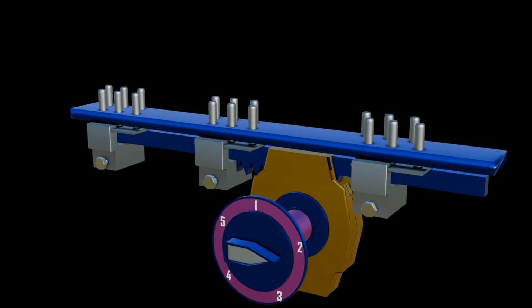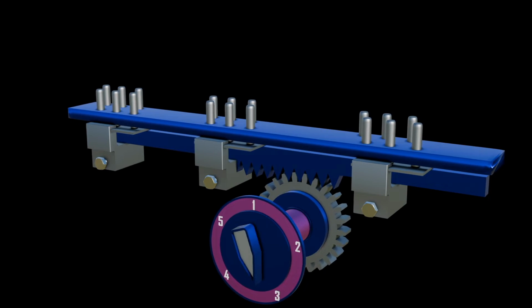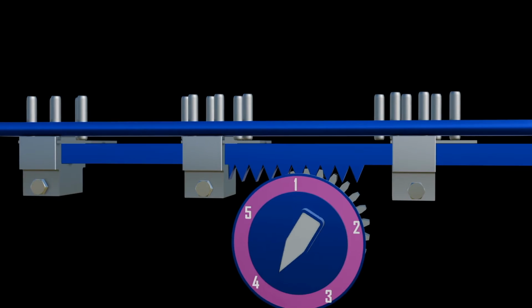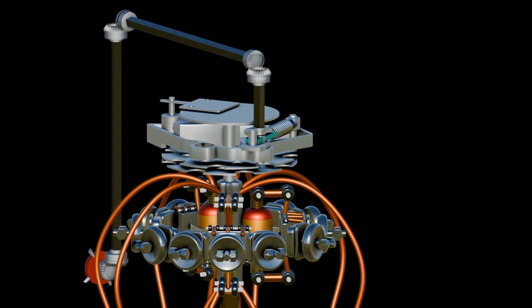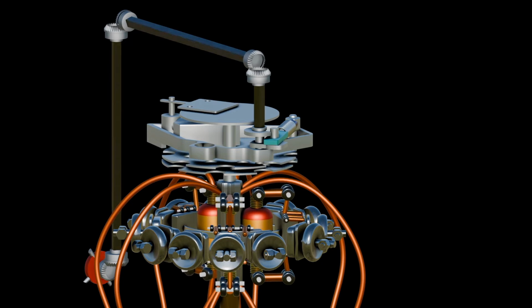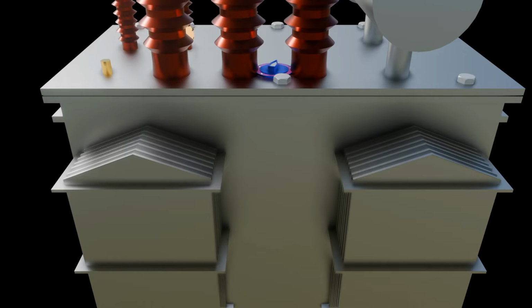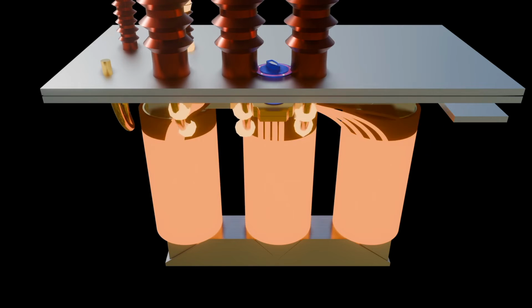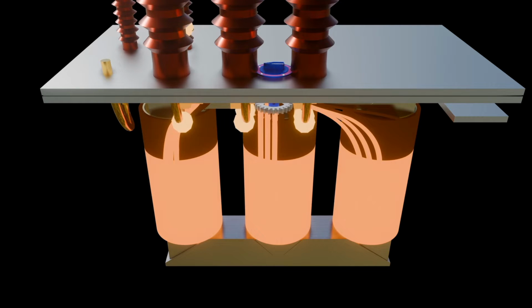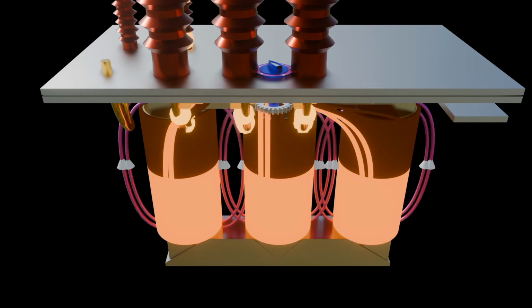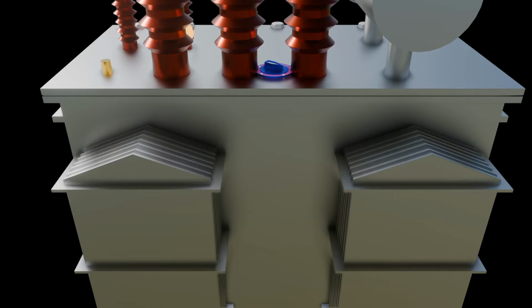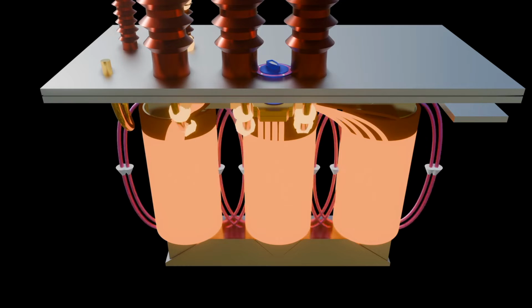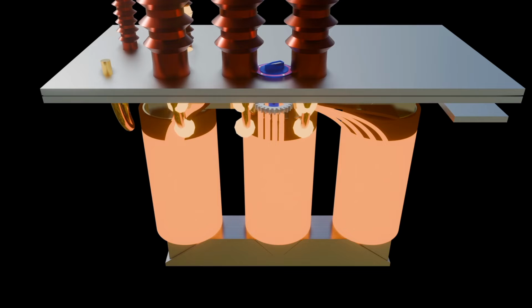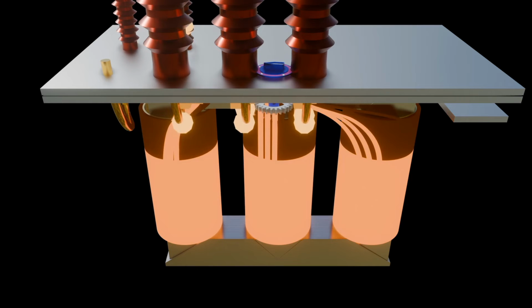There are two categories of transformer tap changers. That is off-load or de-energized tap changer and on-load tap changer. In this video I will brief about the de-energized tap changer, then in my next video, I will talk about the on-load tap changer. Off-load tap changer is a device used in a transformer to adjust the voltage by changing the tap connection without energizing or giving power to the transformer. It is typically used for maintenance or to accommodate varying load conditions.